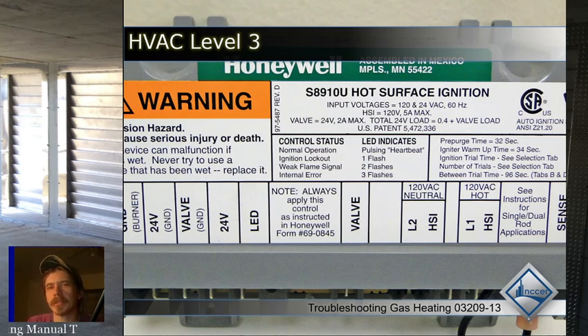But you can place the jumpers at that sub base, and what that does is it tells you, okay, I'm getting power from R to the thermostat sub base, and then it's going to whatever I'm trying to test and getting back to the indoor unit. And if everything operates by jumping it, but it doesn't operate when you put the thermostat on, you know the thermostat's not operating properly. So if you jump R to Y, the outdoor unit will come on, right?